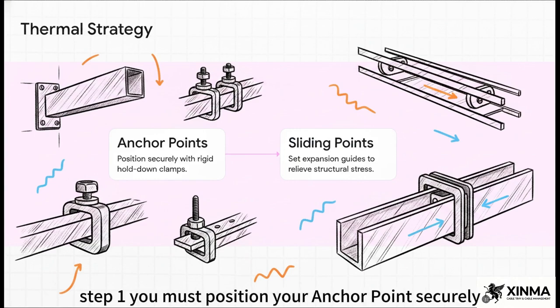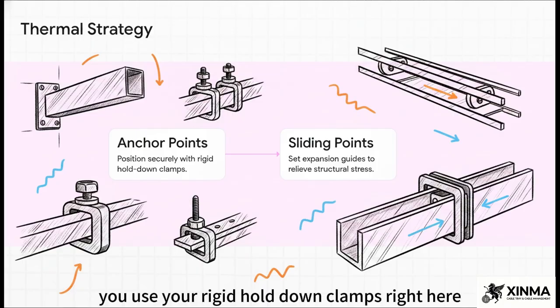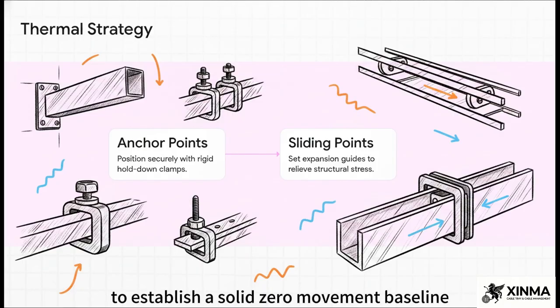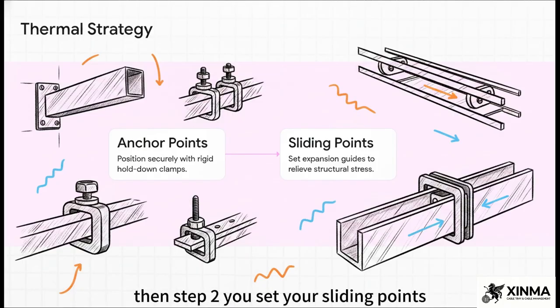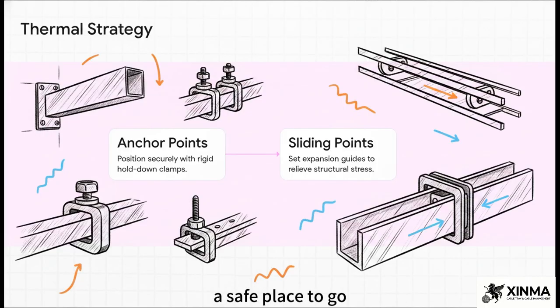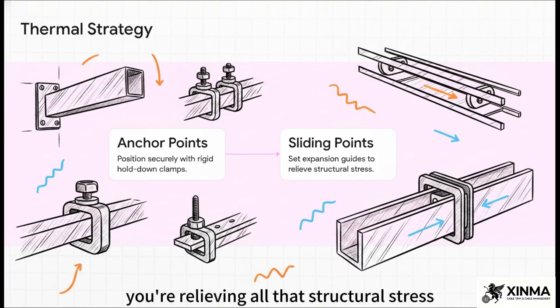Step 1: you must position your anchor point securely, using your rigid hold-down clamps to establish a solid zero-movement baseline. Step 2: you set your sliding points using the expansion guide clamps. By strategically placing these sliding points all along the tray's run, you give that thermal expansion a safe place to go, relieving structural stress by letting the metal naturally expand and contract without snapping the joints.